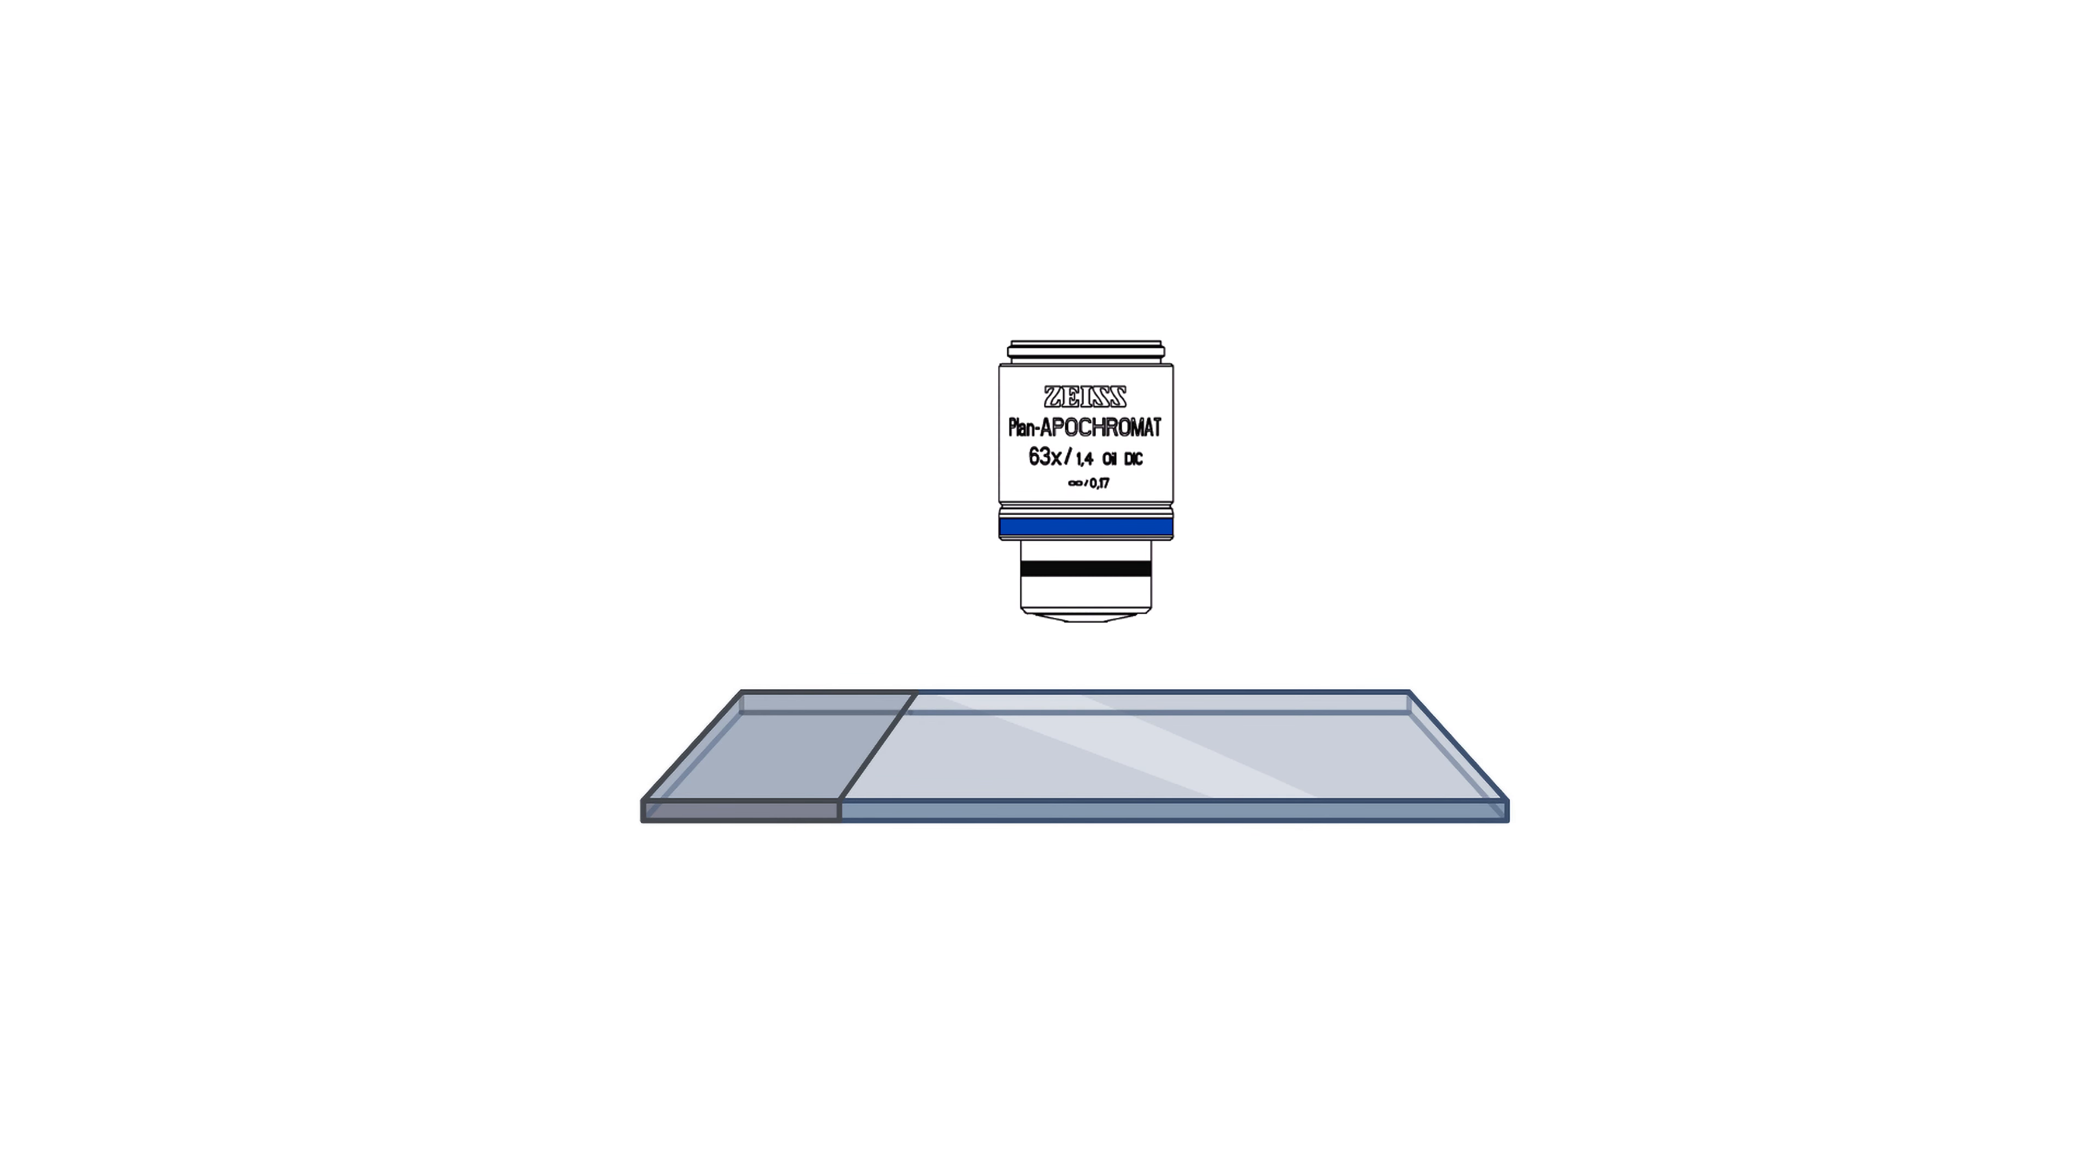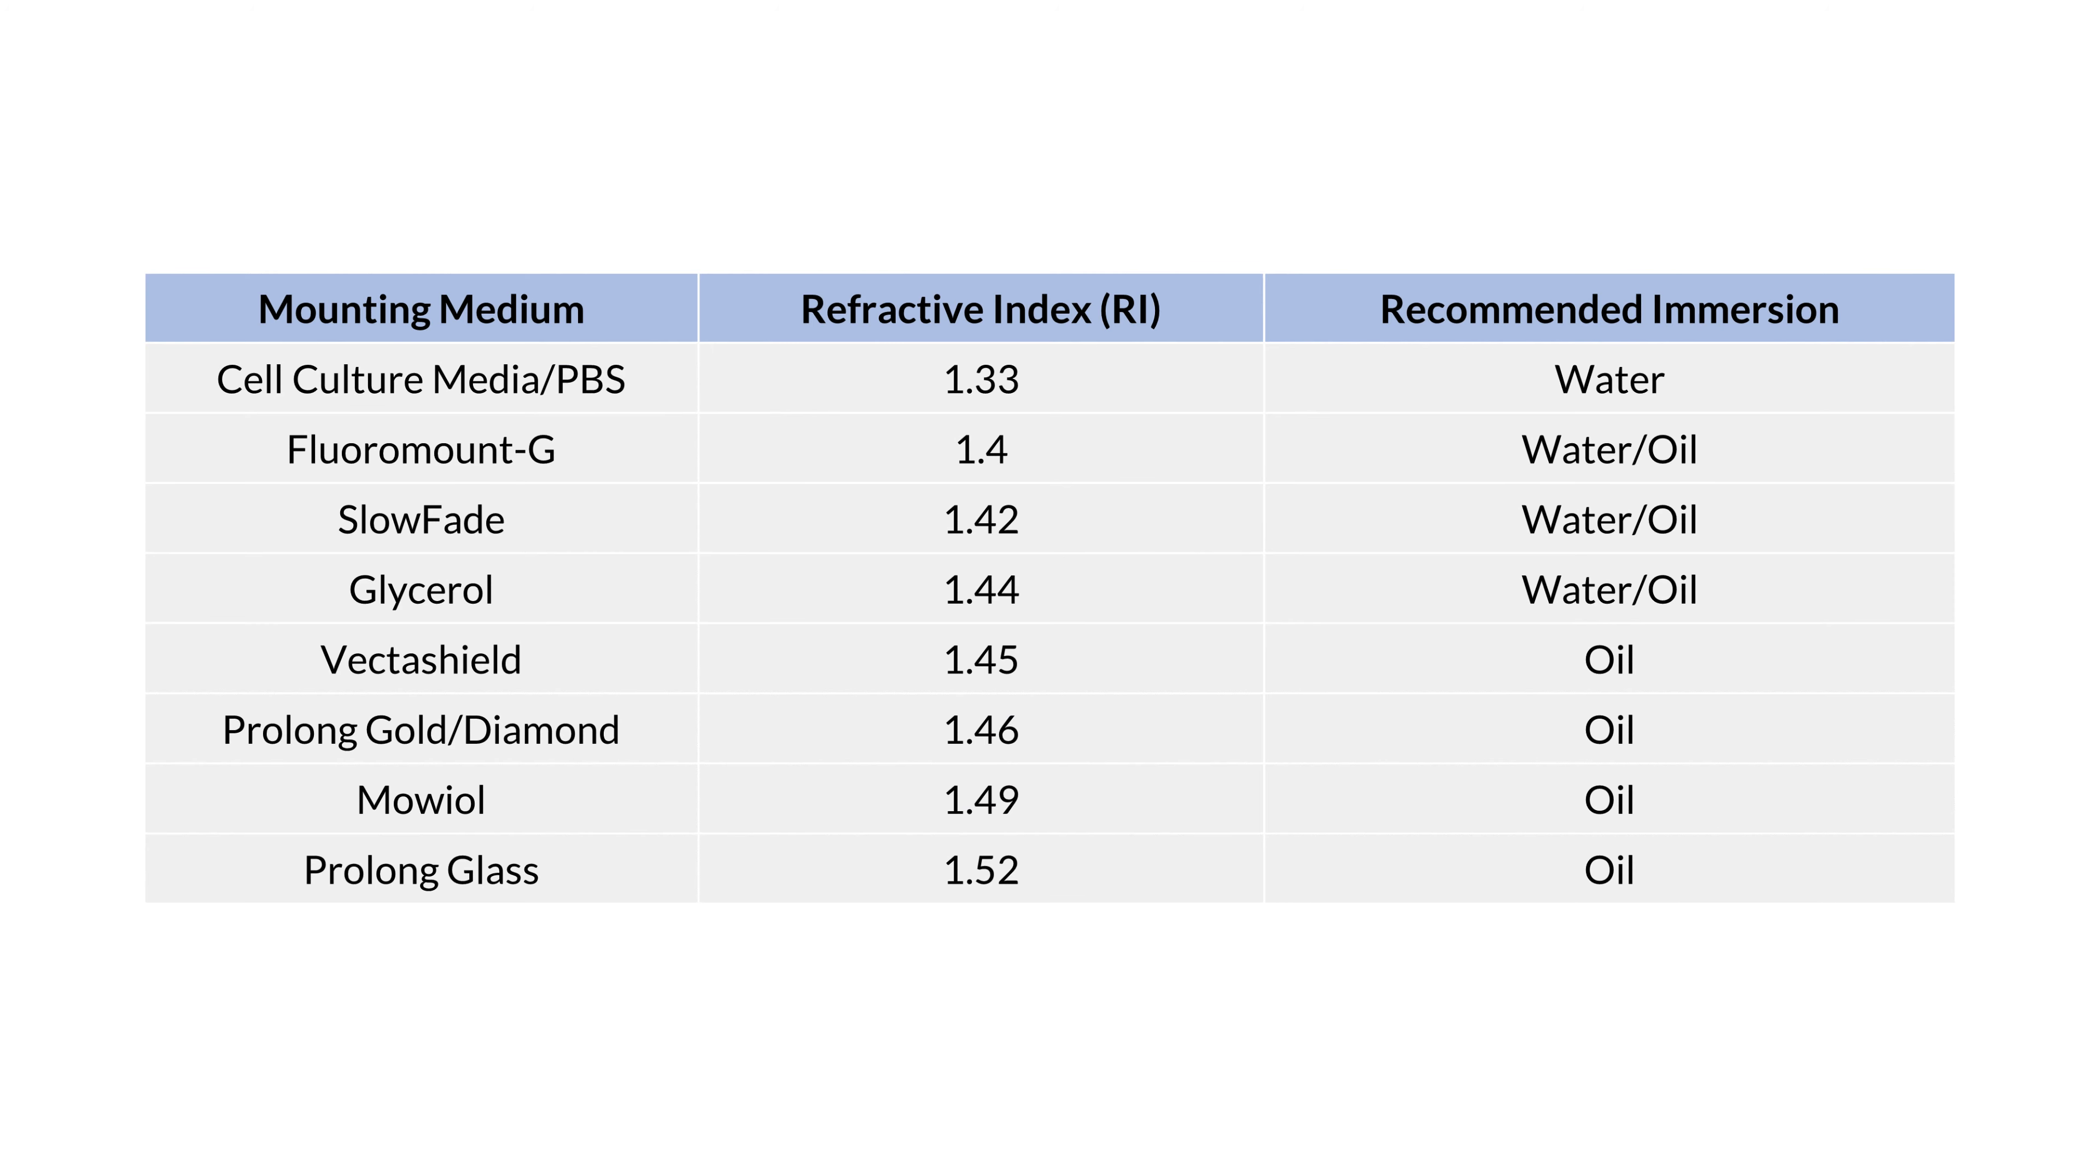If you have tissue sections that are mounted in Prolong Glass, for example, which has a cured refractive index of 1.52, an oil immersion objective would be the best choice. Here is a list of a few common mounting mediums and their refractive indices along with respective immersion fluid recommendations. You can see that many of these mounting solutions have refractive indices somewhere between oil and water. So we want to choose an objective that comes as close as possible to the refractive index of your mounting medium.